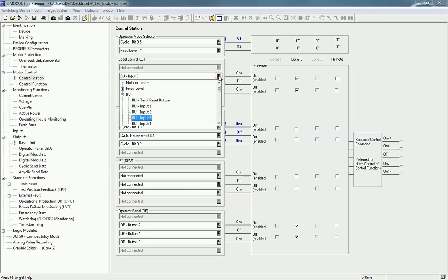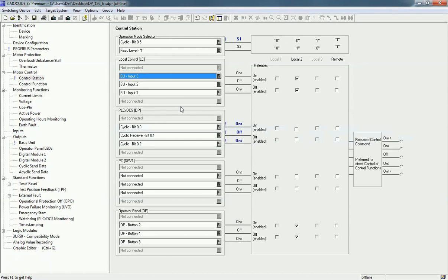When you click on the interconnection, you can configure which inputs you want to use. I will select Input 3, Input 2, and Input 1. Input 3 is for reverse on, Input 2 is for off, and Input 1 is for forward on. Similarly, when using a PLC with cyclic bits, you can use them for reverse on, forward on, or motor off. From the operating panel, buttons 2, 4, and 3 are used for reverse on, off, and forward on respectively.